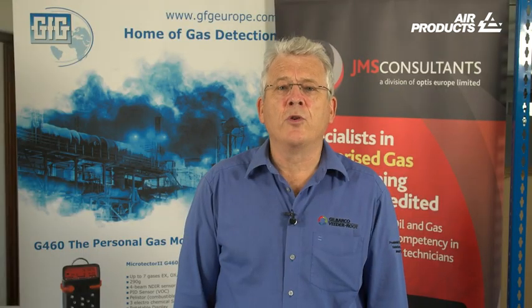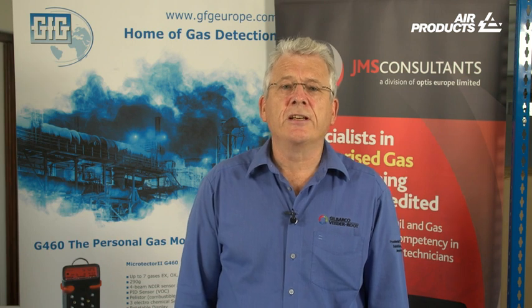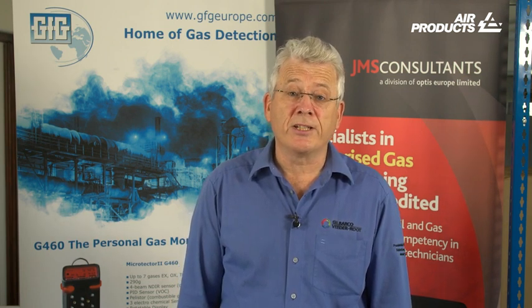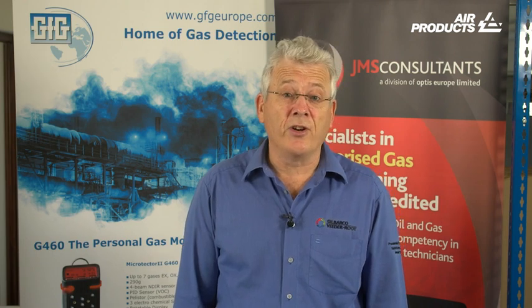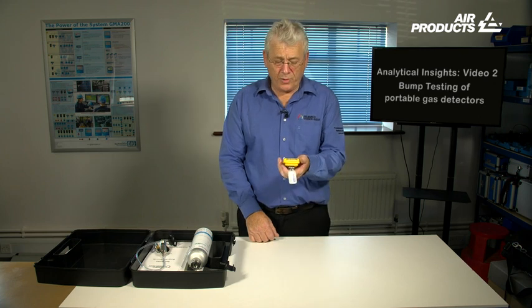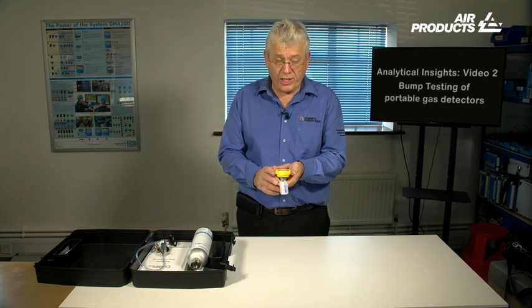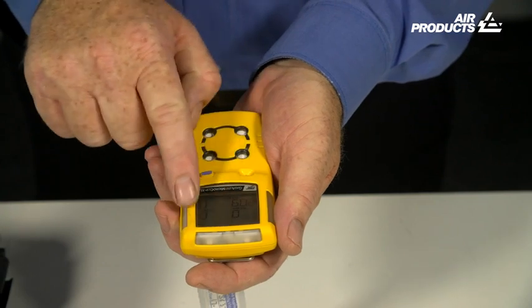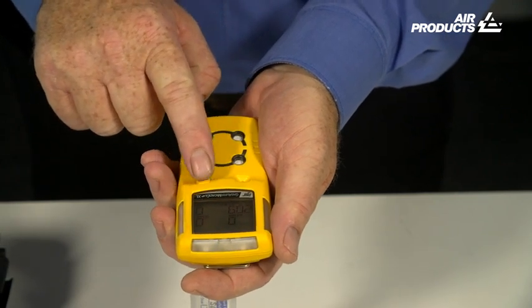At Gilbarco Veeder-Root, all associates who use a gas monitor in the course of their duties have had bump test training, which takes no more than 10 minutes, and the trainers have refresher training on a 3-year cycle. To conduct a manual bump test is very easy. First of all, switch on the device and ensure that all 4 sensors are recording correctly. That's 3 zeros and 20.9 for oxygen.